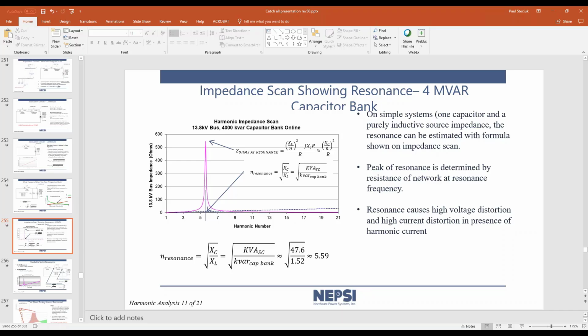If we look at this curve where I have the arrow pointed, that's about the fifth harmonic. At the fifth harmonic, if I were to inject just 1 amp of harmonic current, and this is the key here, this network would experience nearly 550 volts of harmonic voltage distortion. That's line-to-neutral voltage distortion is what that's reading. So when you get an impedance scan generated by EasyPower, if you have it set up correctly, on the left axis you can have ohms, and I'm getting these axes mixed up.